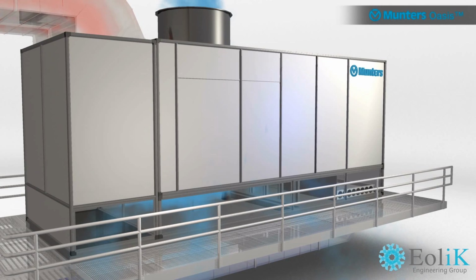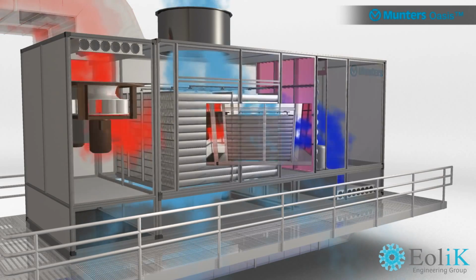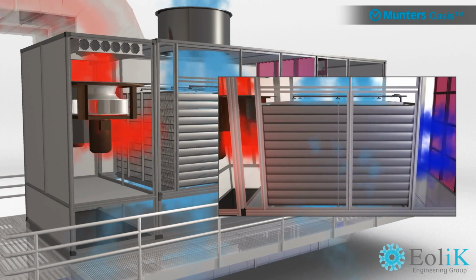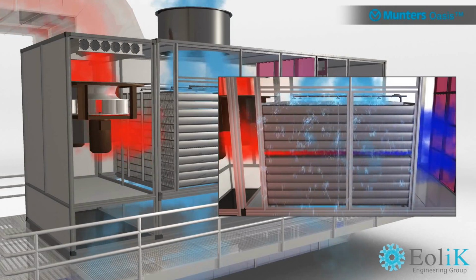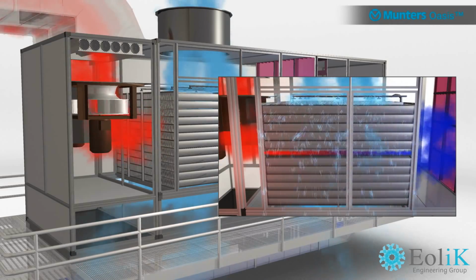Air-to-air energy recovery works by taking two air streams, the outdoor air that's cooler and the indoor air that's heated from the IT equipment, performing a heat exchange between the two without ever mixing them. If the outdoor dry bulb air temperature isn't cool enough to lower the indoor air to the set point temperature, the unit switches into its second method of energy saving operation, as an indirect evaporative air cooler.